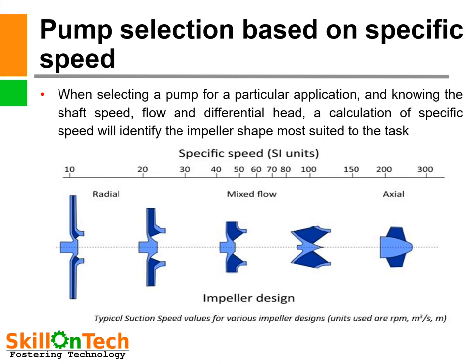When selecting a pump for a particular application, knowing the shaft speed, flow, and differential head, a calculation of specific speed will identify the impeller shape most suited to the task. In SI units, radial flow impellers generally range between specific speed 10 to 40, mixed flow impellers from above 40 to 150, and axial flow impellers from above 150 up to 300. You can decide the shape of the impeller based on the specific speed of the pump.